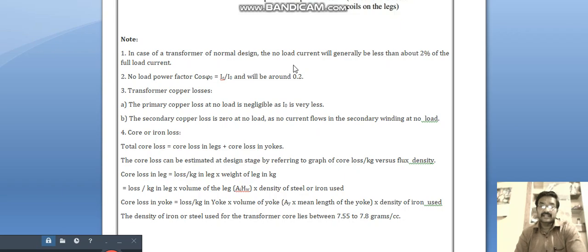Core or iron loss: The total core loss is equal to core loss in legs plus core loss in yokes. The core loss can be estimated at design stage by referring to graph of core loss per kg versus flux density.